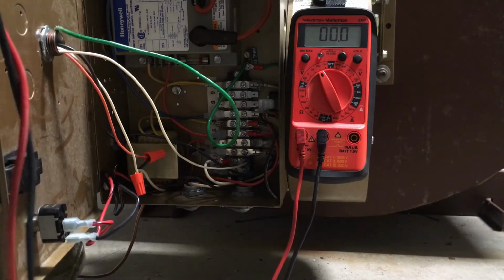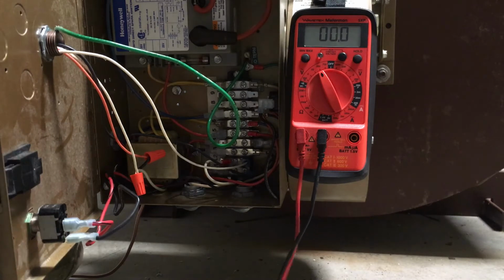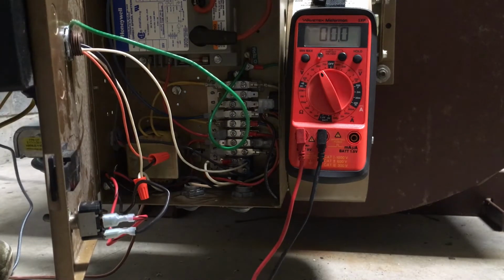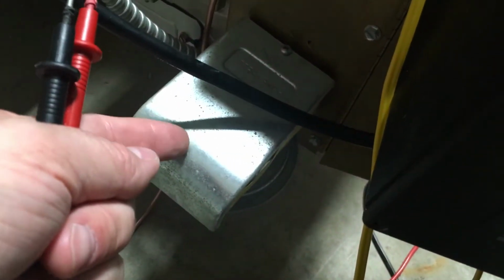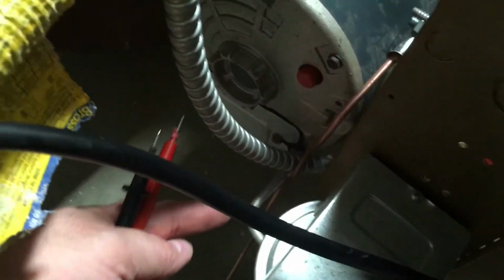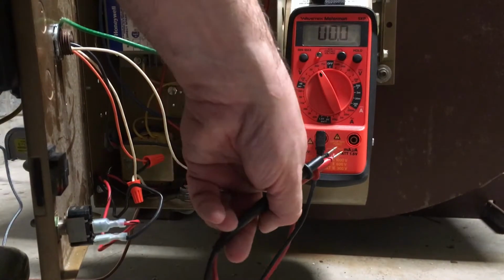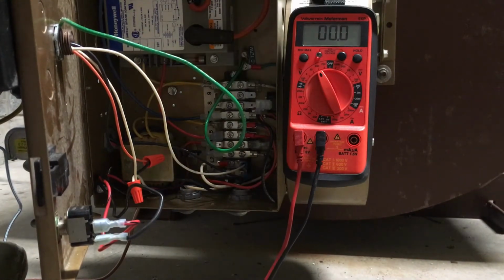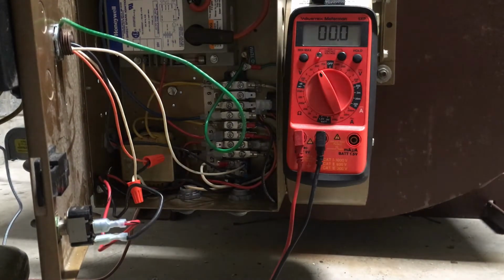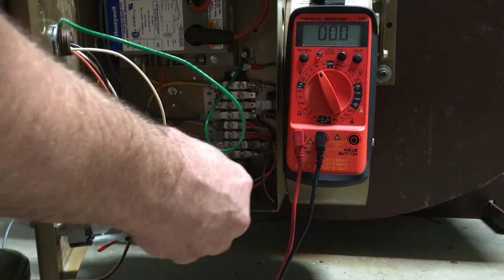And that would be the air interlock switch, the motor interlock switch. That is another thing they call the air proving switch, which is down right here on the side of the control box. And it has a tube that goes into the blower housing. What it does is verify that the blower is operating properly. It's setting the proper air pressure before the system will operate. So again, you're checking terminals 5 and 10.